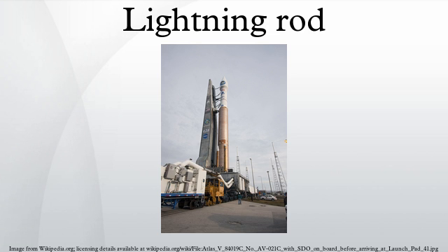The most effective way to prevent this potential damage is to ensure the electrical continuity between the lightning protection system and any objects susceptible to a side flash. Effective bonding will allow the voltage potential of the two objects to rise and fall simultaneously, thereby eliminating any risk of a side flash. Lightning protection system design.